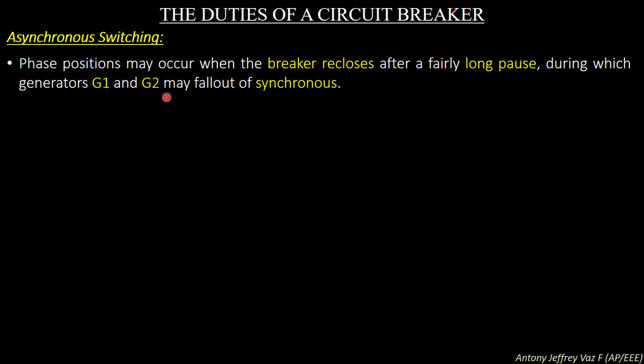When the switch opens, the peak value of TRV is determined by the sum of V1 and V2, and approaches 2 times the short circuit or terminal fault interruption. So when asynchronous switching is made, the total value will be determined by the voltage produced by generator 1 and also the voltage produced by generator 2. When these two values are added, it will be like a short circuit current or a short circuit voltage. It will also be like a terminal fault interruption process.